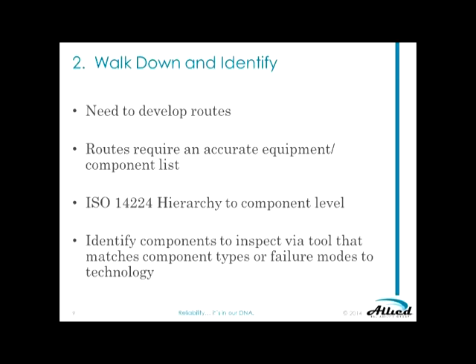To do this, one of the things you may need to do up front is make sure you've got a good equipment hierarchy to organize these routes in. If it's ISO 14224 compliant, that makes things a heck of a lot easier. I've been working with a couple of clients on that in the past two years, one being a major automaker, making sure we've got a good compliant hierarchy so when we set up our maintenance plans and routes for ultrasound, we know somebody's charging time to doing those routes and we're getting information back that says, gee, we found an air leak here, or these particular steam traps were identified as blowing through.